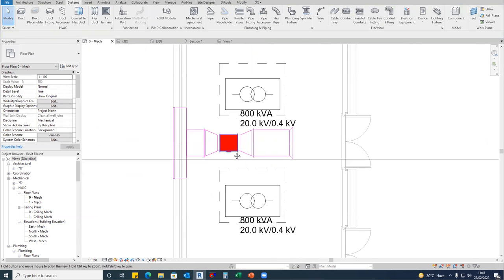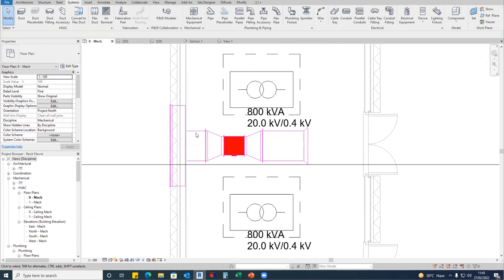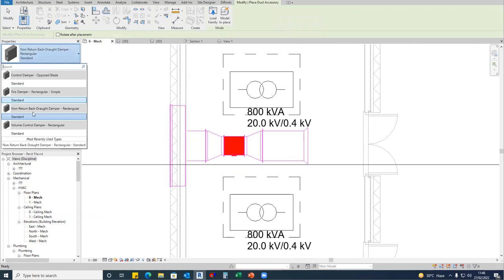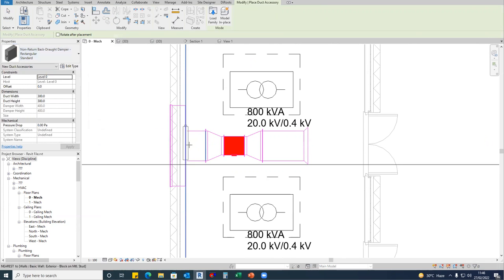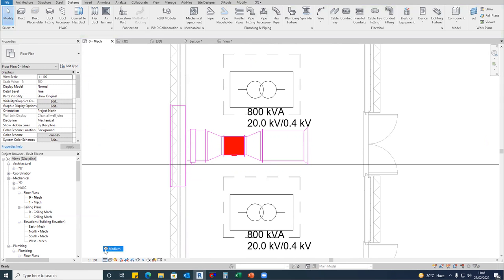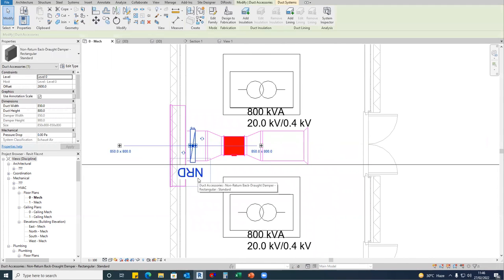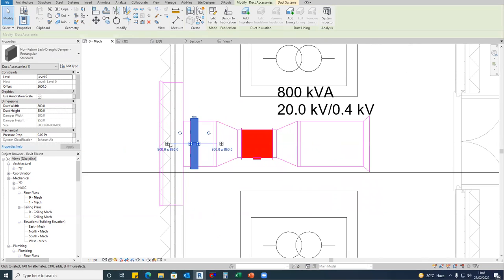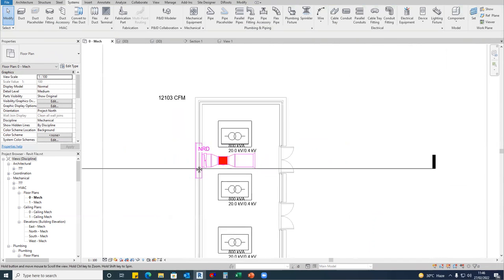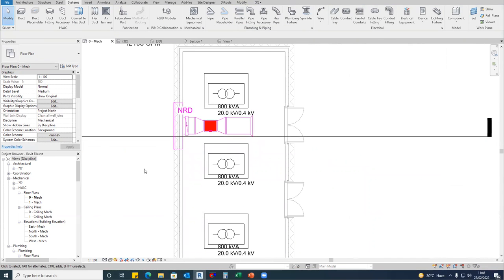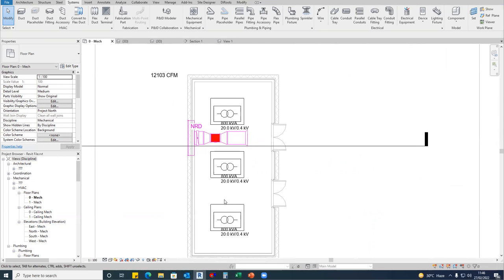Okay, fine. Now before this, you must place the NRD also, the exhaust. Okay, so I'll go to the duct accessories. Here I have non-return damper. Select this non-return damper and place it over here. Okay, make it medium and just rotate this again. So we have an NRD. Okay, now this arrangement is okay, fine.